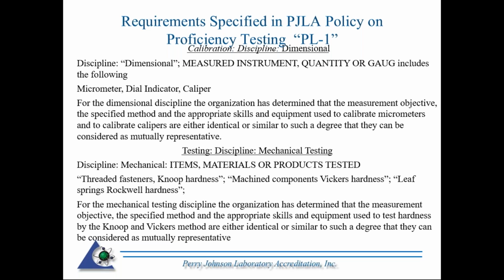The organization has determined that the measurement objectives, specified method, and appropriate skills and equipment used to calibrate micrometers, calipers, and dial indicators are either identical or similar enough to be considered mutually representative. So if you're shown proficient through a test on a caliper, that can be crosswalked over favorably. If you can do the caliper, you can do the dial indicator and the micrometer as well.